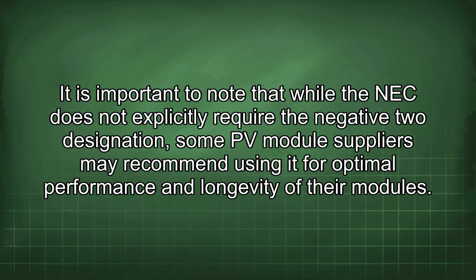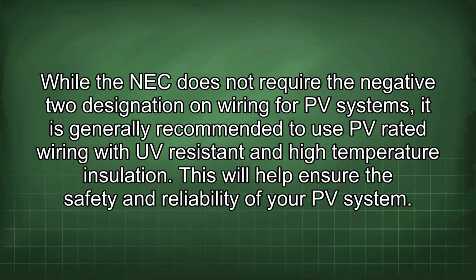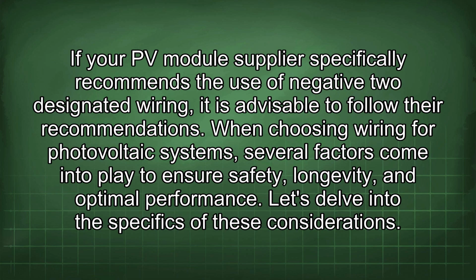It is important to note that while the NEC does not explicitly require the -2 designation, some PV module suppliers may recommend using it for optimal performance and longevity of their modules. While the NEC does not require the -2 designation on wiring for PV systems, it is generally recommended to use PV-rated wiring with UV-resistant and high-temperature insulation. This will help ensure the safety and reliability of your PV system. If your PV module supplier specifically recommends the use of -2 designated wiring, it is advisable to follow their recommendations.